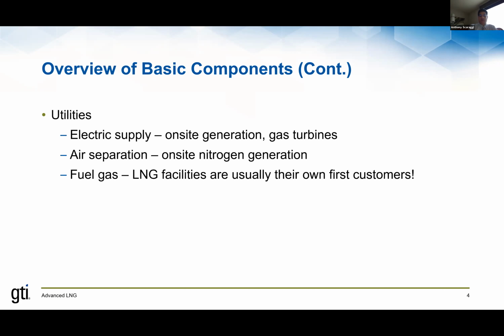And nitrogen is used to purge systems and piping of natural gas before work is done on those systems, so it can be done in a manner where the workers are not exposed to natural gas and possibly the hazards associated with that, normally being that natural gas is flammable. Also, when you put a system back into service, you generally purge, depending on the size of the system. But one of the normal considerations is whether or not you purge the air out of the piping or out of the components before you introduce natural gas back into those systems, so that you don't have a combustible mixture in the equipment or in the pipe while you're reintroducing natural gas into the system.